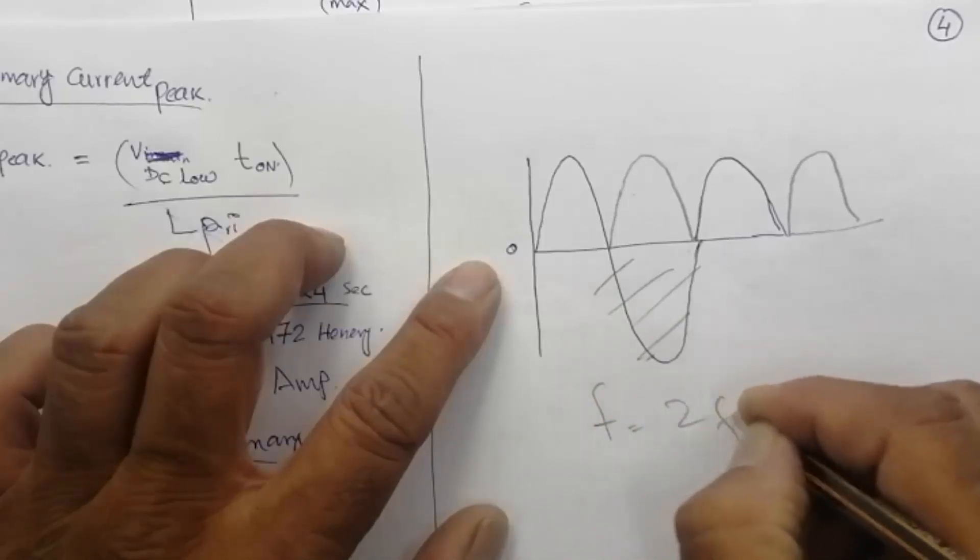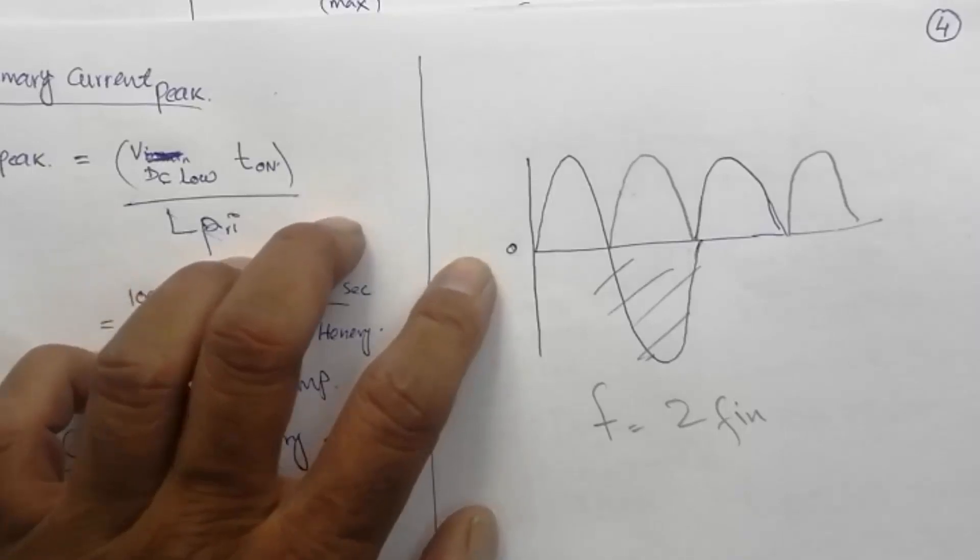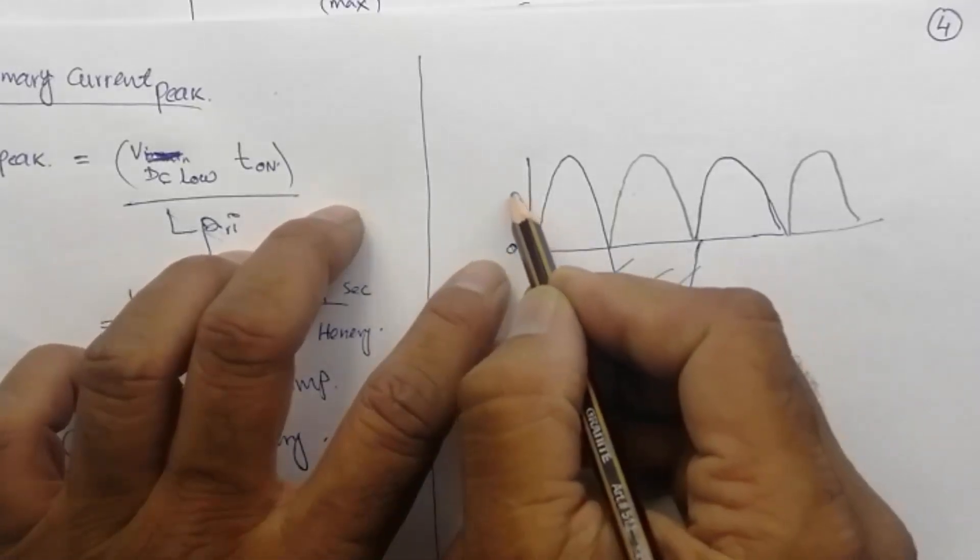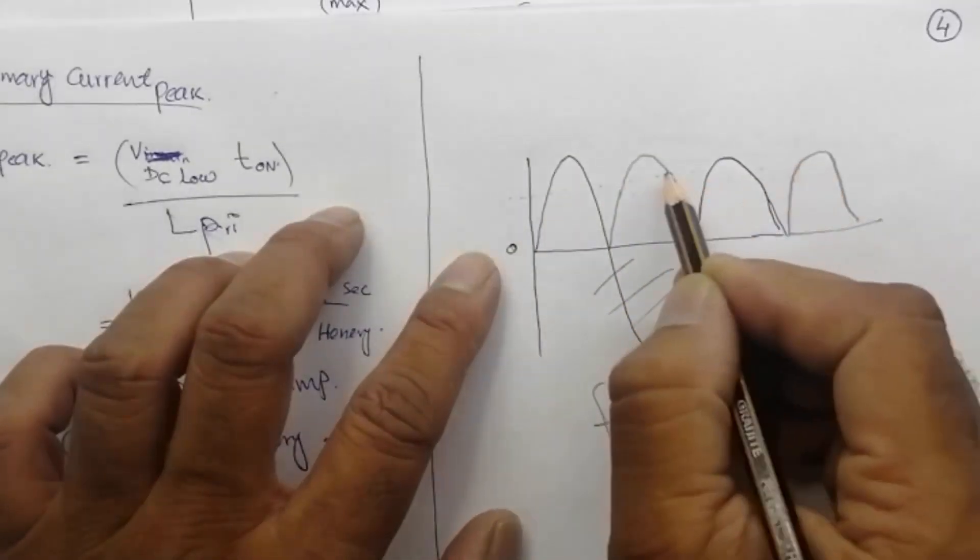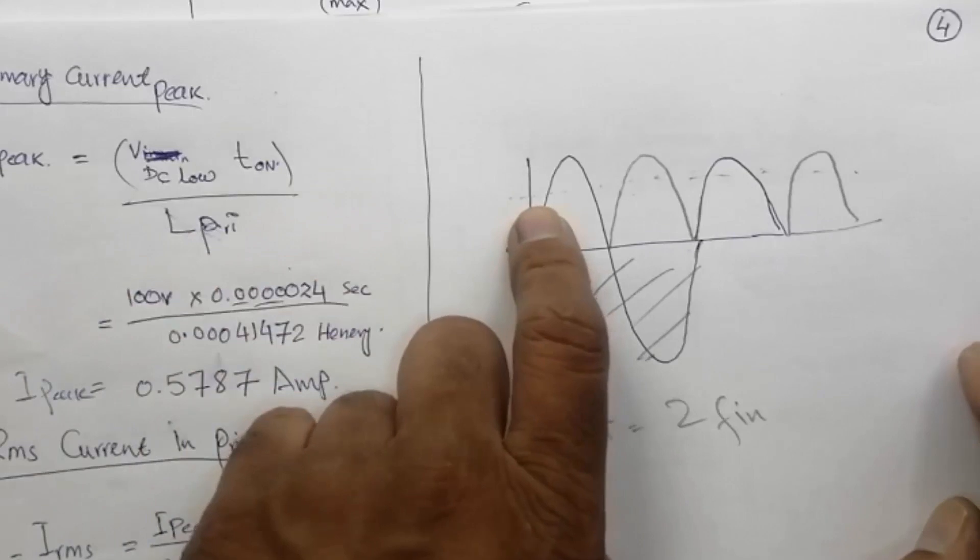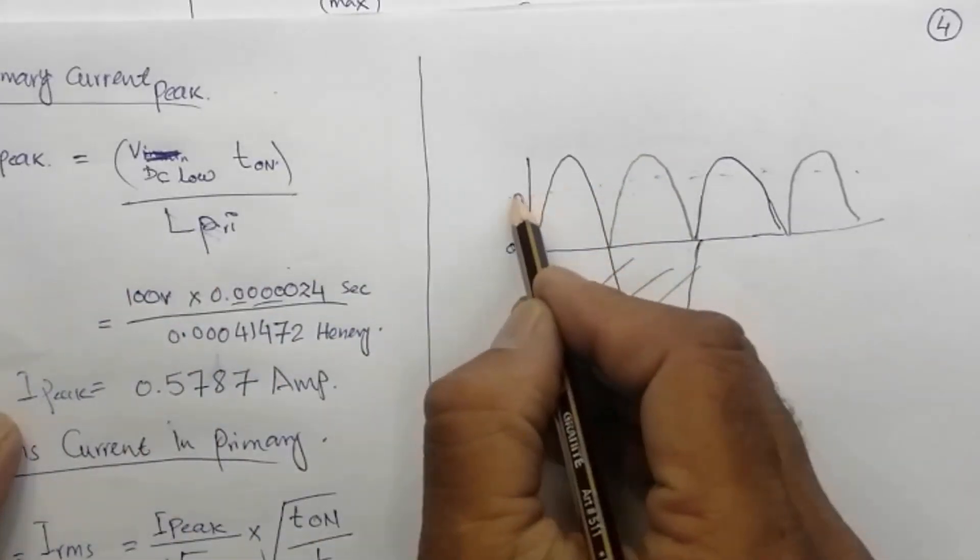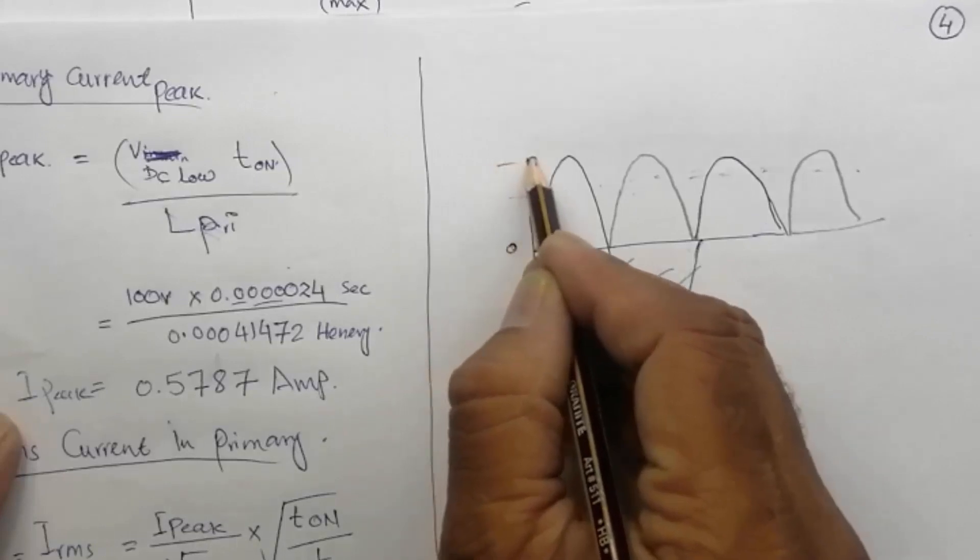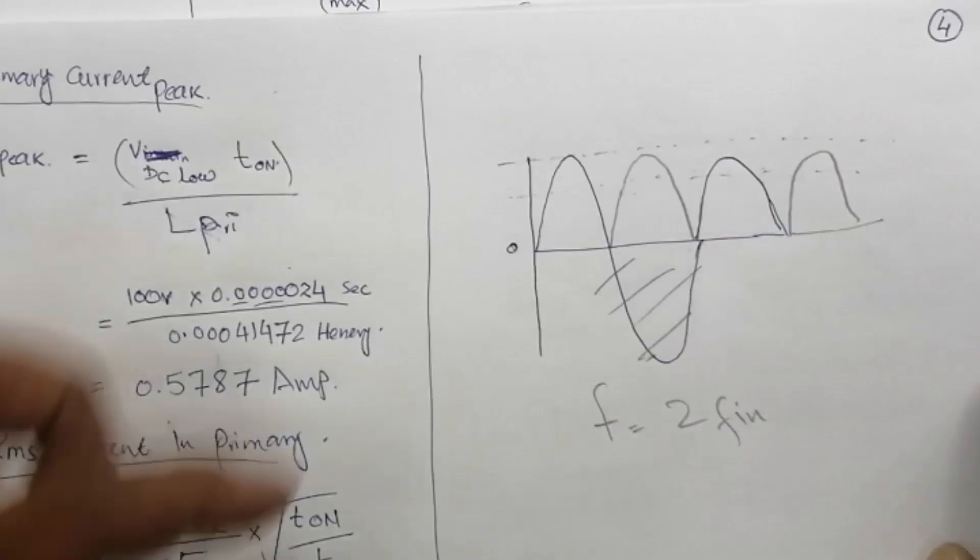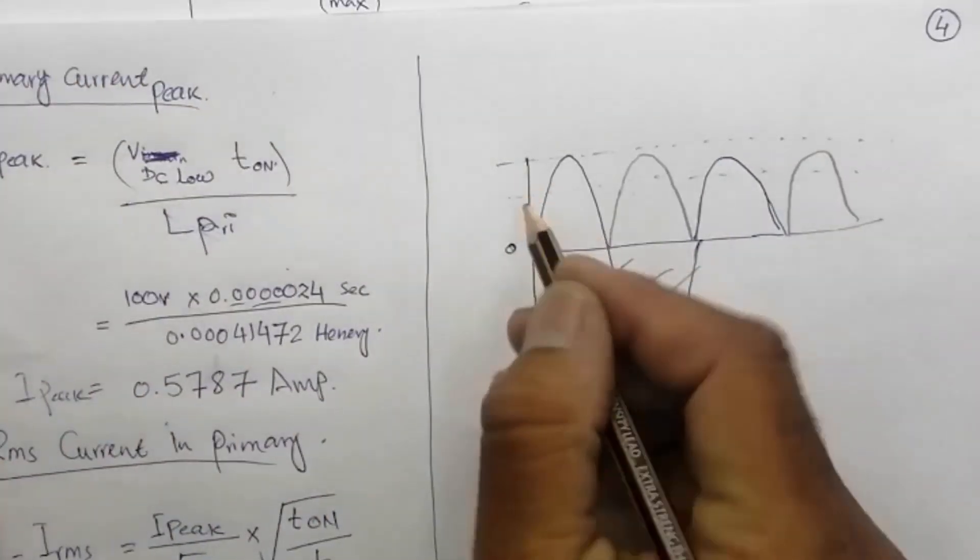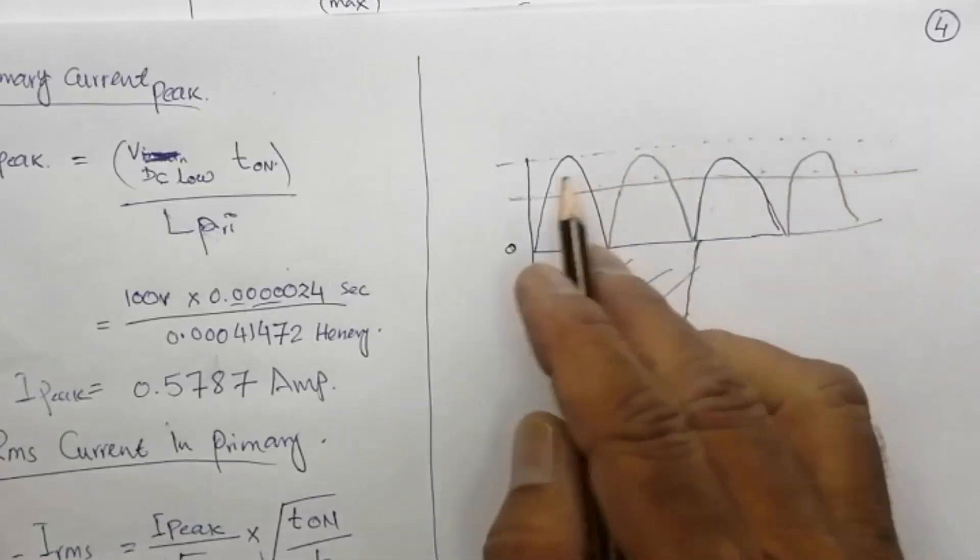So here the frequency will be 2f. Now the RMS value will be here, but in our calculation when we select a bulk capacitor, we take the top level, the highest peak.